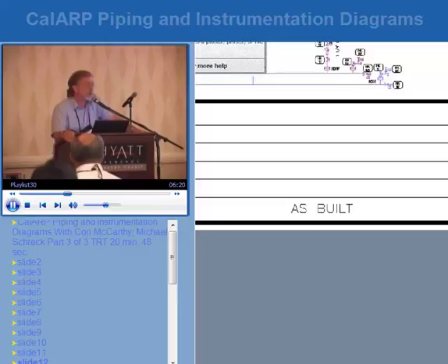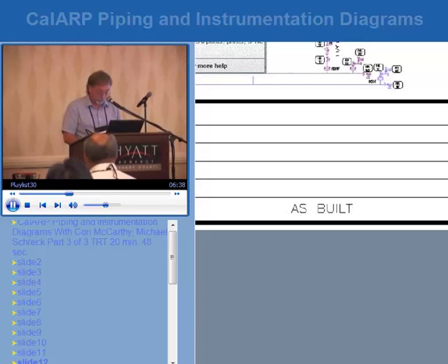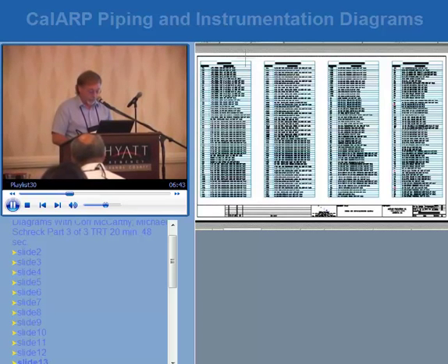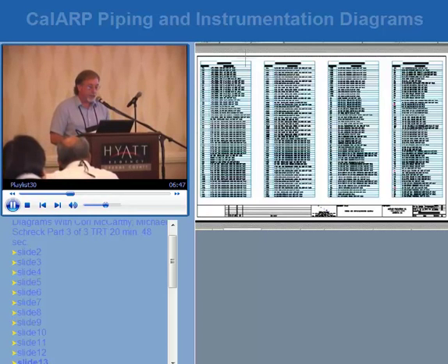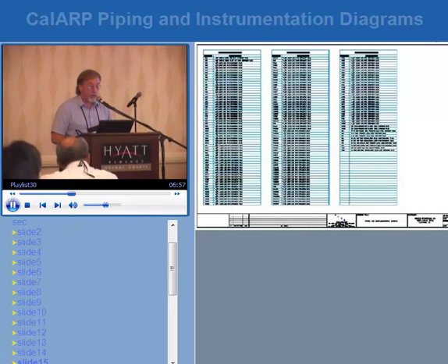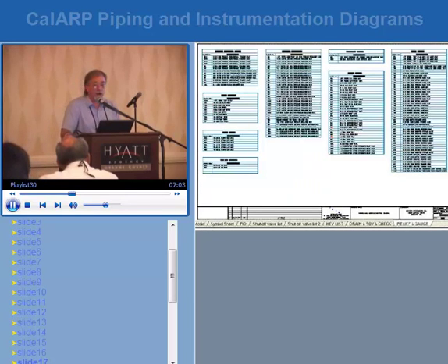The valve list can get quite extensive — there can be thousands of valves on a large plant. The list will cover shutoff valves, stop valves, hand expansion valves, drain valves, solenoids, check valves, relief and gauge valves. They need to have it in a format that the operator can easily follow. Then on the main drawing we'll break it down — using connector arrows or diamonds to show where a line continues to another drawing, with the line size, operating conditions, the drawing reference number, and the line number shown at the breakpoint.